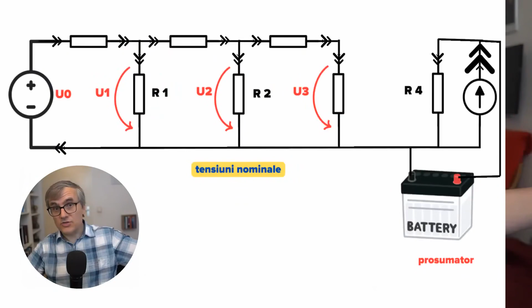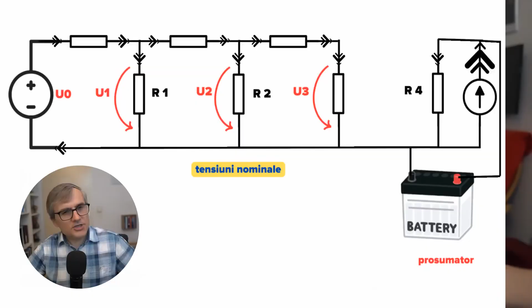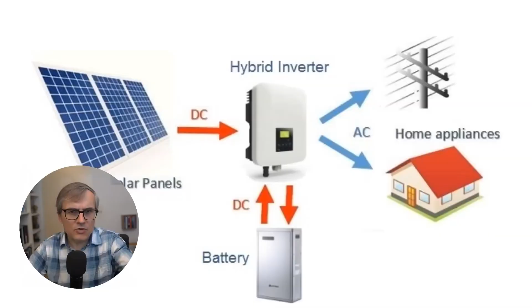However, there are other solutions as well, such as using batteries. This is easy to understand. If the voltage rises too much when the surplus energy is delivered to the grid and the inverter is disconnected from the grid, it can automatically connect to the batteries and charge them. The energy stored in the batteries is then delivered to the grid at the most suitable time. For example, in the evening when the panels are not charging the battery, when consumption is high and the system needs energy. In fact, with batteries, you can do something even smarter. If you automatically check the weather and see that it will rain tomorrow, it's better not to put the battery energy into the grid, but to keep it for yourself. Use it the next day.